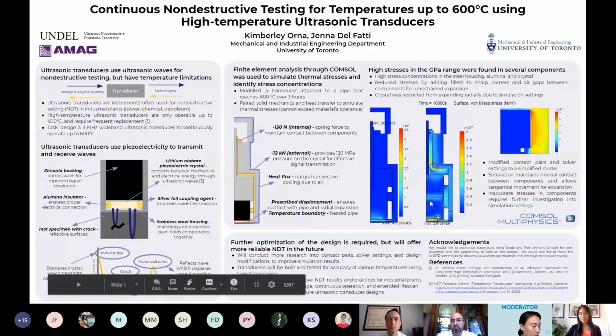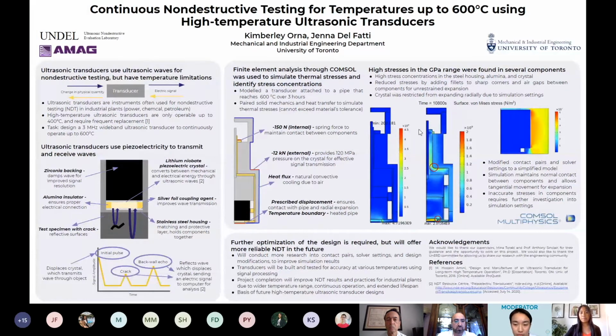As you can see, here are two of our possible designs. This was our first one, and we noticed that there were really high stresses all the way to the gigapascal range, which was unacceptable. So we used some basic stress decreasing techniques, I guess you would say, such as adding fillets to the sharp corners, adding in some air gaps for more expansion. It helped somewhat.